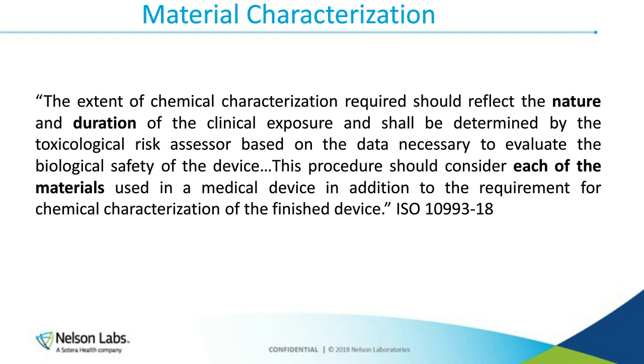So I want to focus on that for a minute. This allows us to determine, okay, what's our contact with the patient, what's our risk, and how far do we need to assess that? So right here is where we are going to decide if we do extractables and leachables testing, or if we can do a literature review, or if we have good supplier information on this material that we're choosing to use, and how invasive or how extreme is our manufacturing process? How many compounds are we using? Do we do a cleaning validation? You can see that you kind of go in many different directions when we're looking at material characterization.